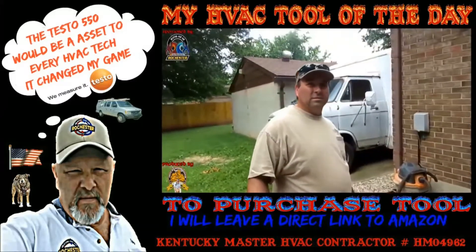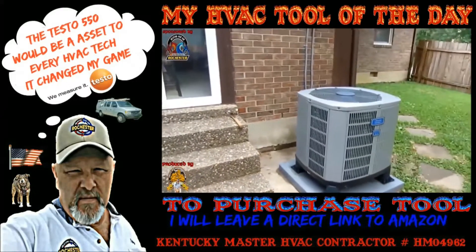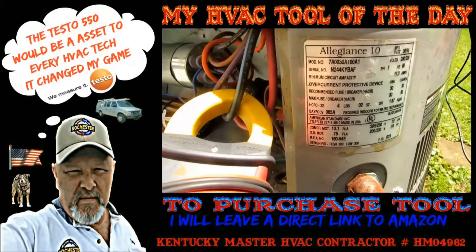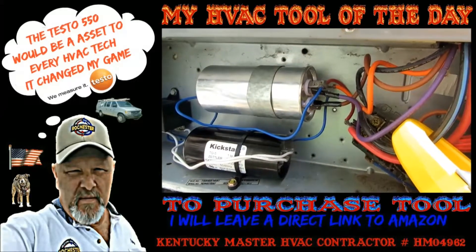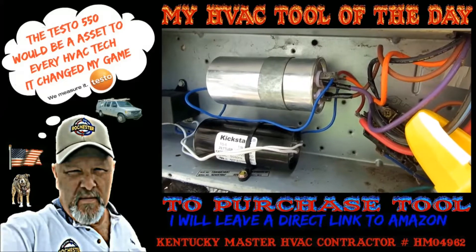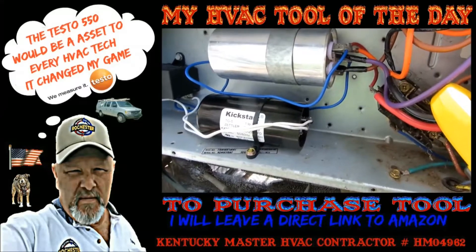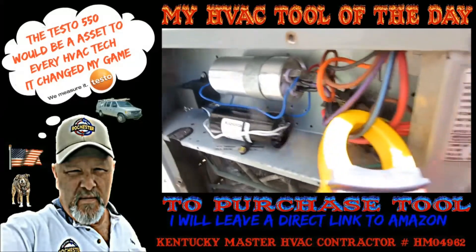Alright Carl, I reckon we're done here today buddy. We got your 11 and I think we're tight, we got her good and clean - it's a 98 model so we're roughly about 18 years old. What I merely did was I came in, I slapped on a capacitor - 45/5, I had 5 micro farads on the fan side, 45 on the herm side - and I went ahead and I installed a kickstart. As soon as I put the kickstart on, the compressor immediately fired up.